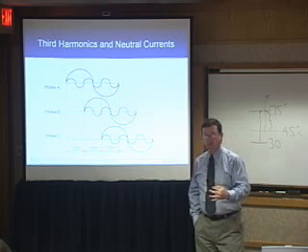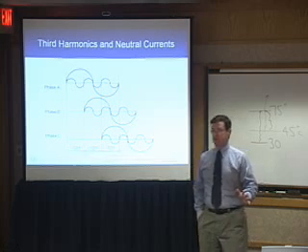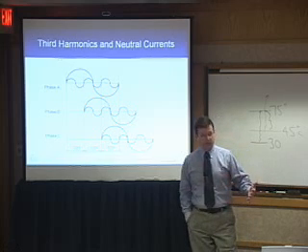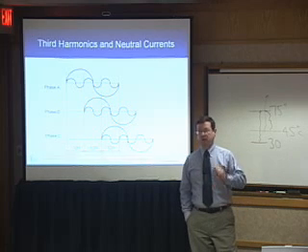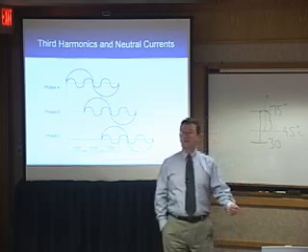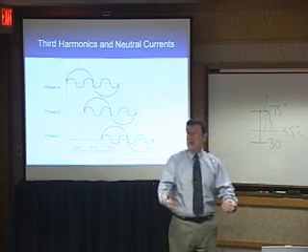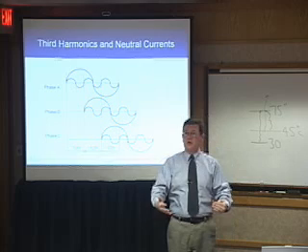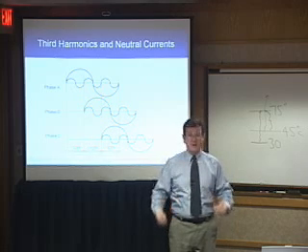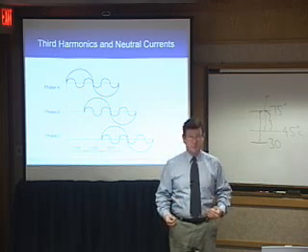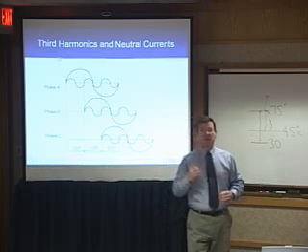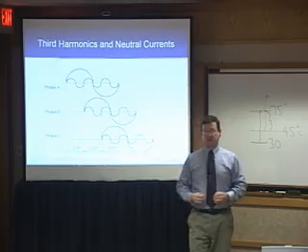It is possible — and I've measured this numerous times through all my power quality measurements over the years — to have more current in the neutral conductor than you do in the phase conductor. Not only is the neutral carrying current in addition to the three phases, it can even carry more current than the phase conductors. Sometimes you actually have to oversize the neutral to carry this additional current from the third harmonics.